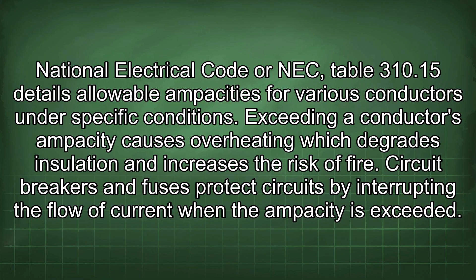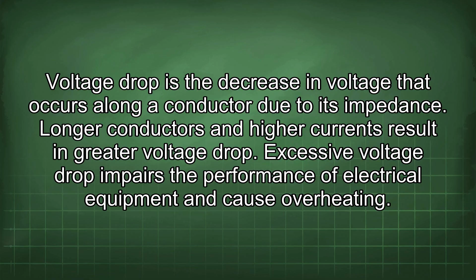Voltage drop is the decrease in voltage that occurs along a conductor due to its impedance. Longer conductors and higher currents result in greater voltage drop. Excessive voltage drop impairs the performance of electrical equipment and causes overheating. The National Electrical Code, or NEC, recommends limiting voltage drop to a maximum of 5% for branch circuits and feeders. Using larger conductors minimizes voltage drop.